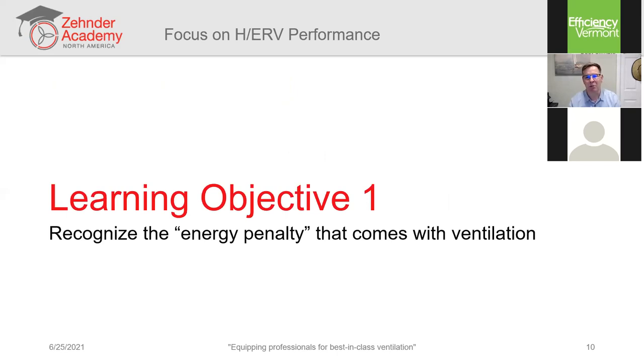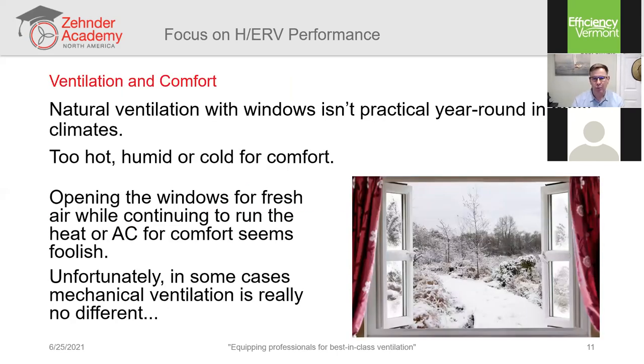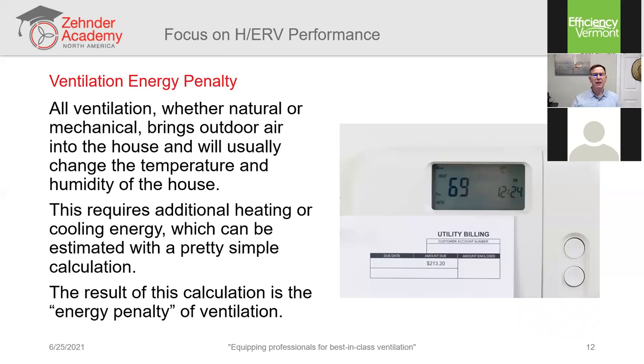Opening the windows to ventilate a building, particularly in Vermont, is not practical — it's usually too hot, too humid, or too cold. It would be counterproductive to open the windows and run the furnace or AC. Yet a lot of mechanical ventilation does essentially the same thing: adding outdoor air at its outdoor temperature and then paying to heat or cool it. This costs money — all ventilation brings outdoor air in at outdoor temperature, requiring additional heating or cooling.